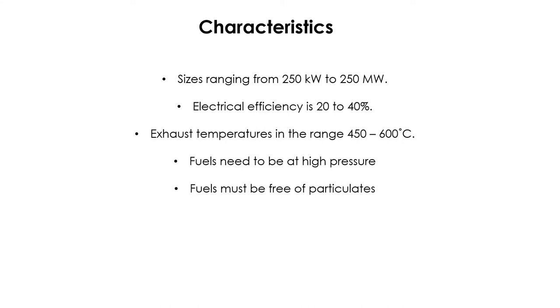The exhaust temperature is pretty high, around 450 to 600 degrees Celsius. The fuels need to be at high pressure and must be free from particulate or sulfur, because particulate can damage the blade and sulfur can corrode the blade as well.